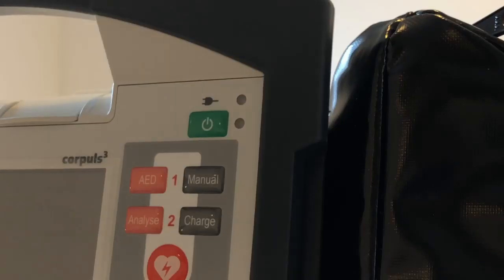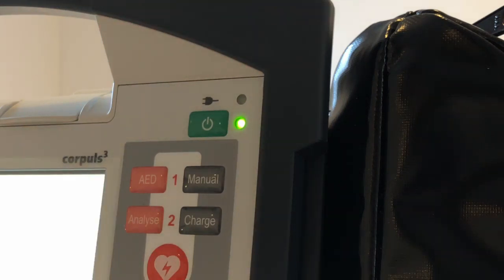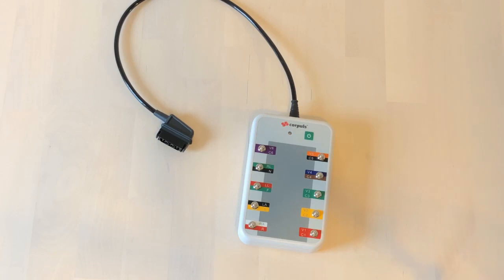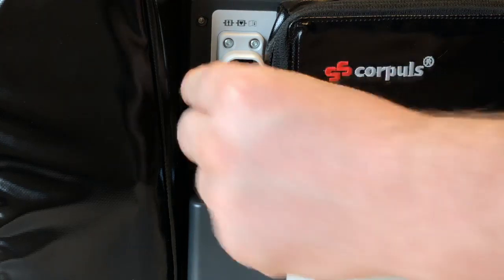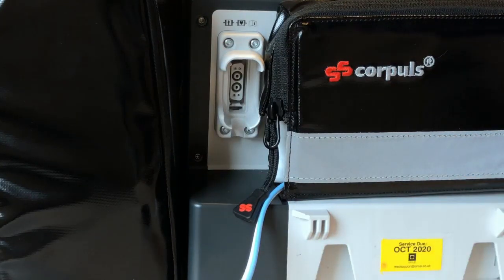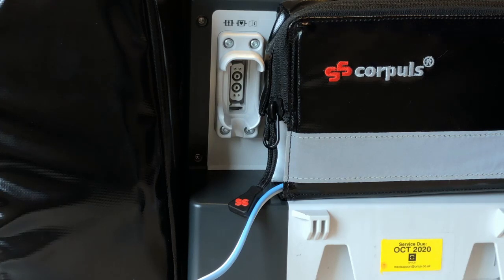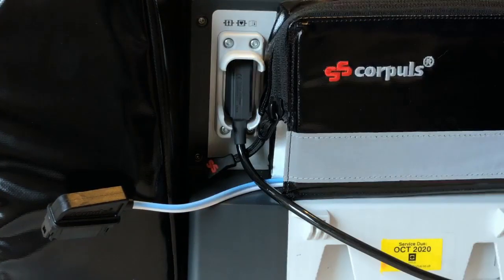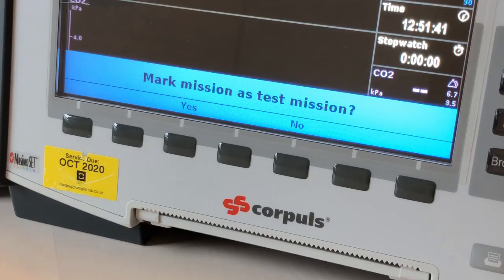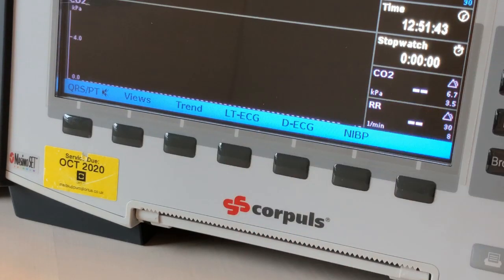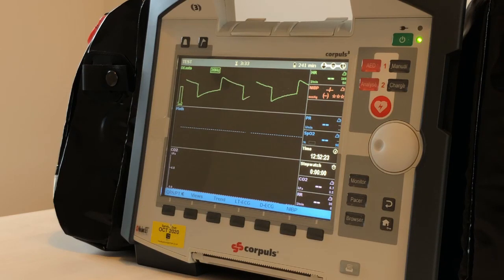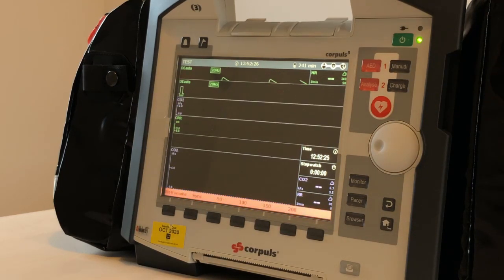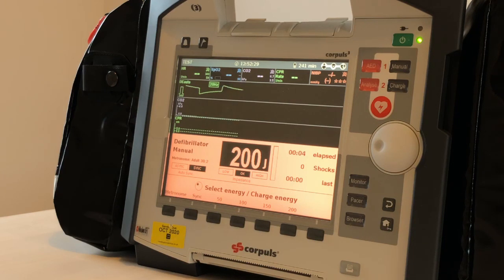Begin by powering on the Corpuls3 and allowing it to complete a self-test. Turn on the test box and then plug the test box into the defibrillator pad socket. Mark this mission as a test mission and switch the device into manual defibrillator mode. Charge to 200 joules and deliver a shock.